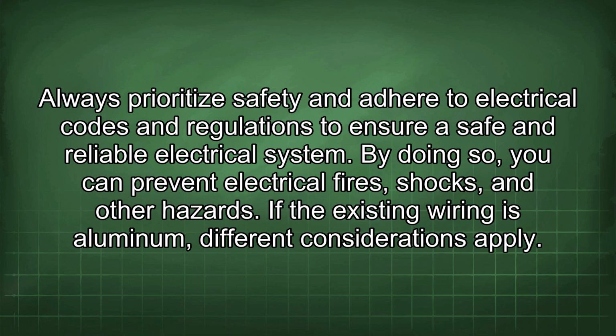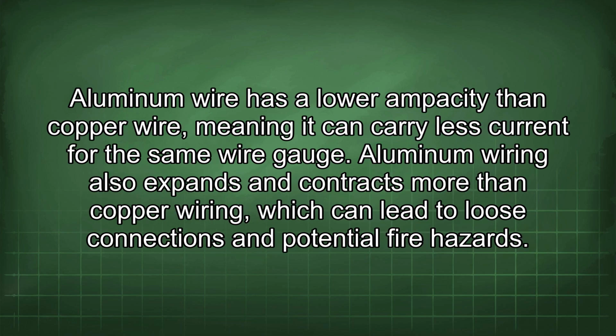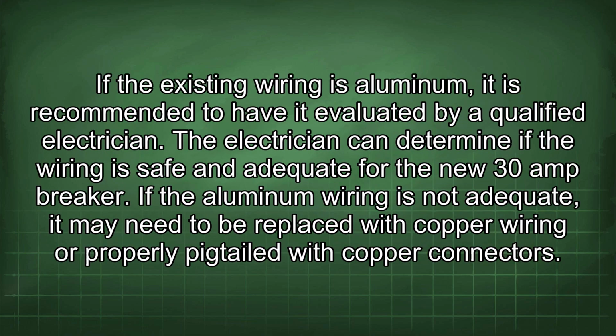If the existing wiring is aluminum, different considerations apply. Aluminum wire has a lower ampacity than copper wire, meaning it can carry less current for the same wire gauge. Aluminum wiring also expands and contracts more than copper wiring, which can lead to loose connections and potential fire hazards. If the existing wiring is aluminum, it is recommended to have it evaluated by a qualified electrician. The electrician can determine if the wiring is safe and adequate for the new 30 amp breaker.